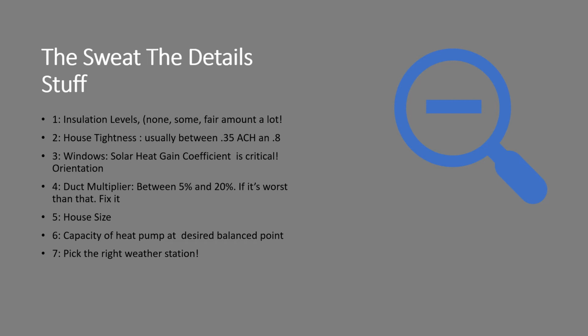House tightness here in the Northwest, it typically ranges from 1/3 of an ACH up to 0.8. New construction is probably going to be closer to 0.2. If your software tells you have an ACH of 2, something is probably wrong. That would be a barn with the doors open on a windy day. Windows, our solar heat gain coefficient is absolutely critical. In the Northwest, if you know the U value, say you have a U value of your window of 0.4, the solar heat gain coefficient is also pretty close to 0.4. A lot of software out there guesses a little too high at the solar heat gain coefficient, which pads the cooling load a little too much.